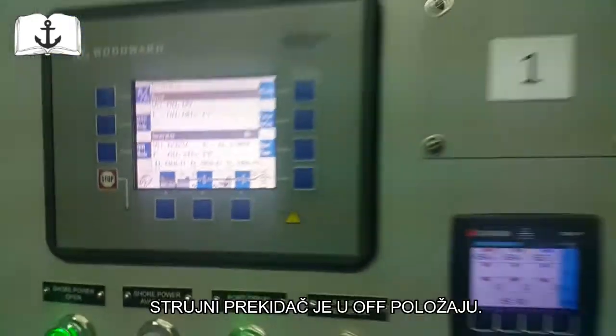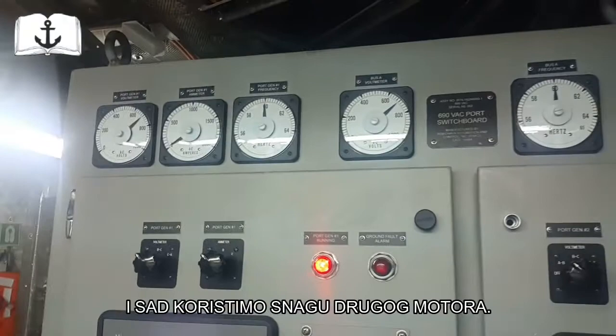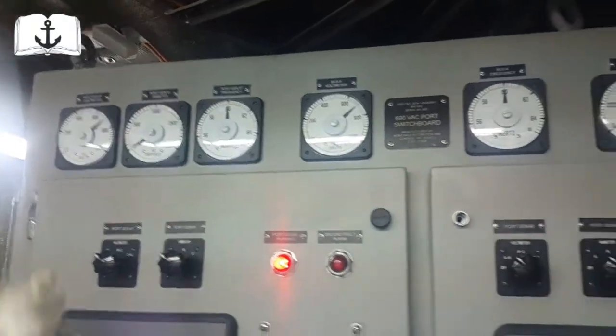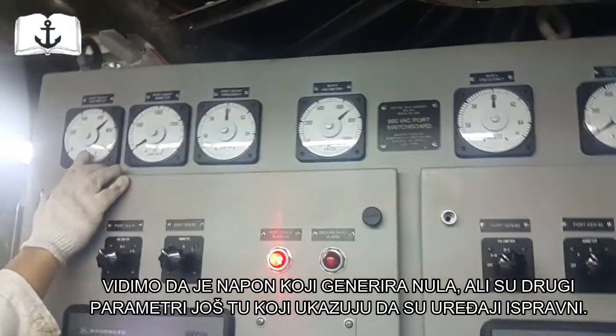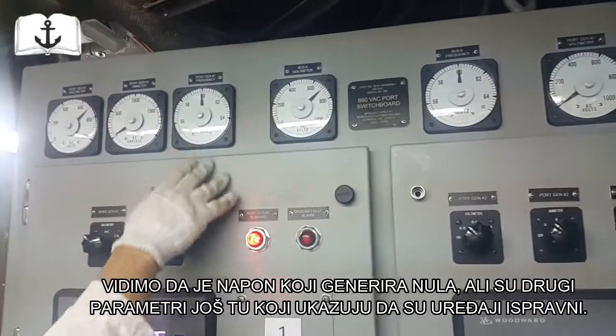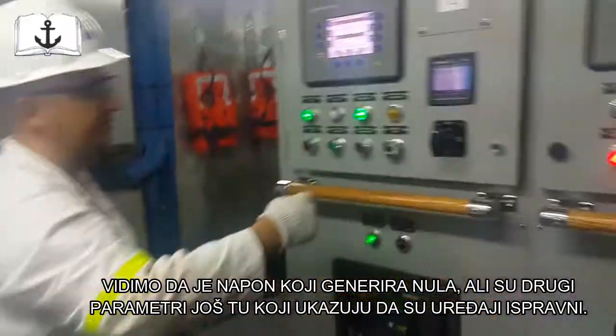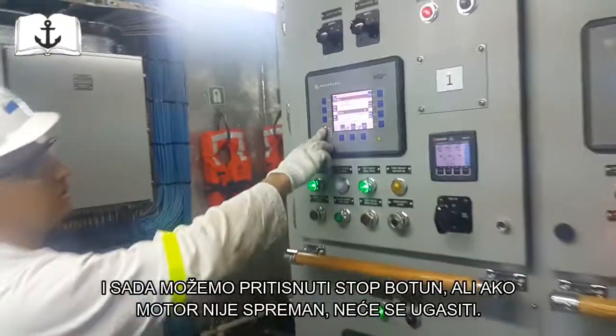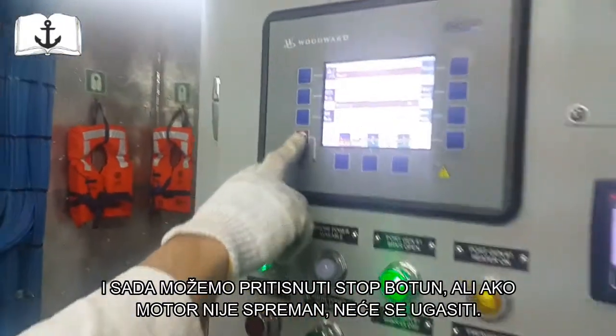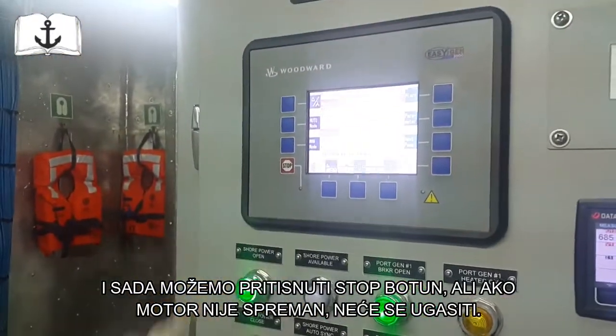Yeah. So the breaker is off. Breaker is off. Yes. And we are on the other engine on the power. And you see the current is off. Still there are the volts and the hertz, because it's showing, like I say, the healthy alternator. And now you're pushing the stop button. You can't do it straight, because this system is so smart. It will not allow you to stop the engine straight.